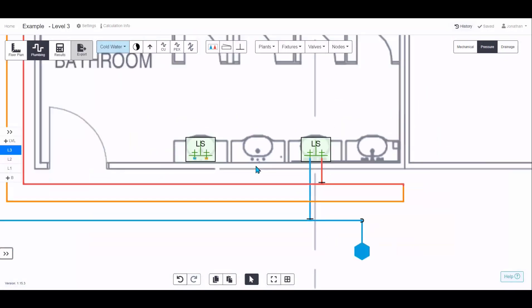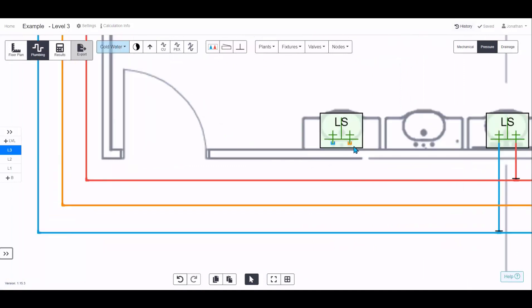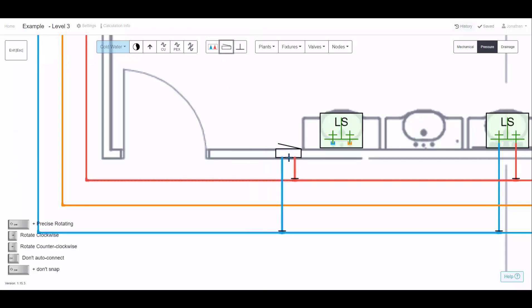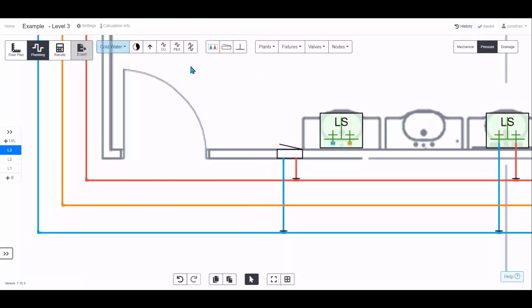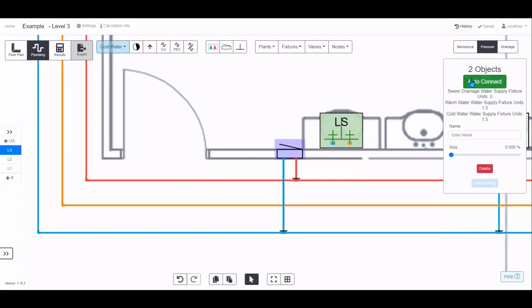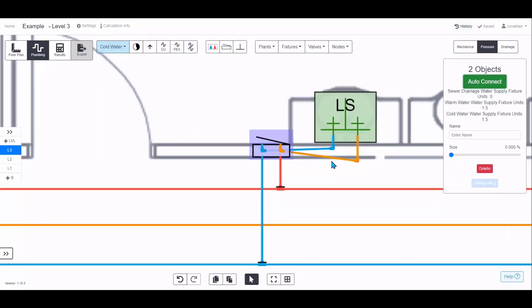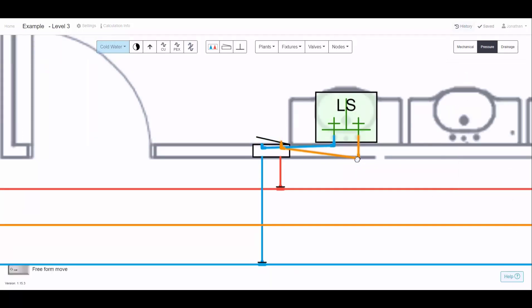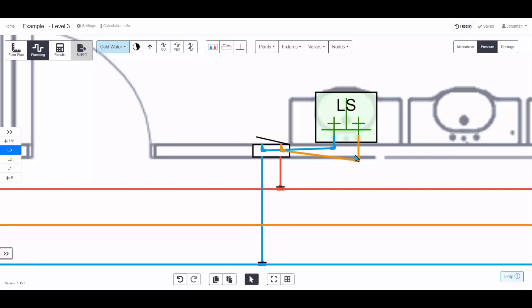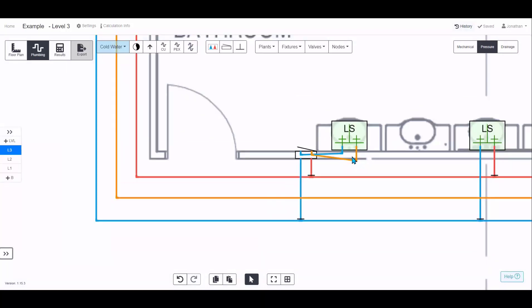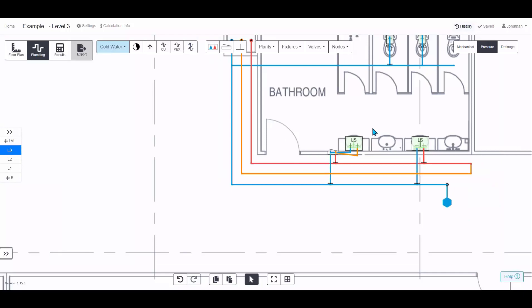Alternatively, if you want to keep it as a warm water connection, use TMVs or tempering valves — these snap to the nearest pipes. You can then auto-connect, though the pipes aren't always straight in tight situations. If you want to be fully accurate, manually drawing the pipes is a great option.